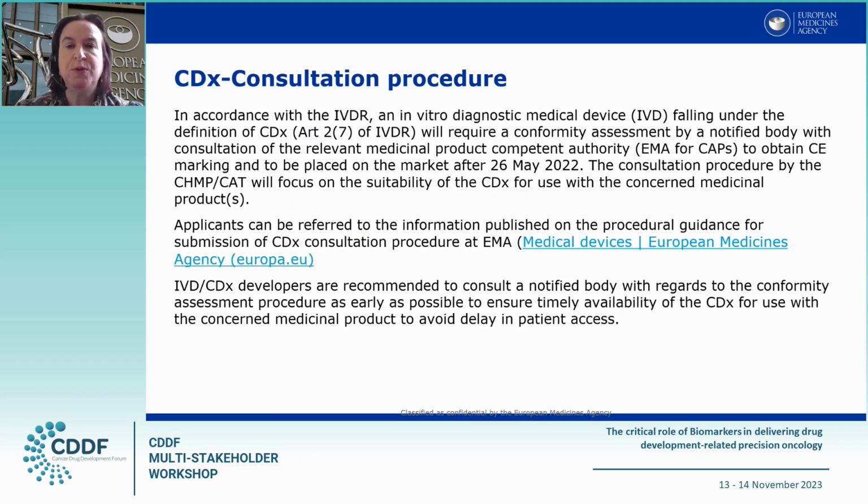When we move to the consultation procedure for companion diagnostics, the conformity assessment as described in the legislation mentions that for companion diagnostics, the notified body shall consult the concerned competent authority, in this case, the European Medicines Agency as applicable.